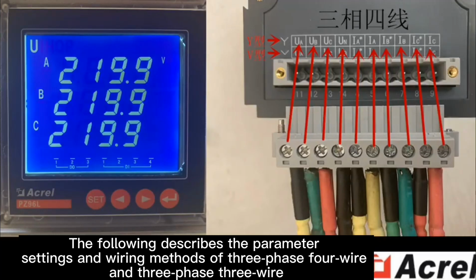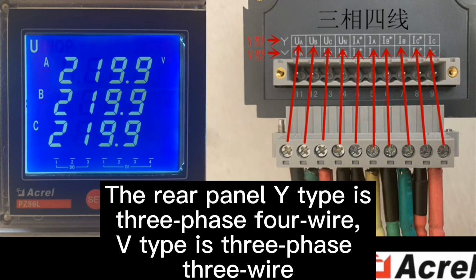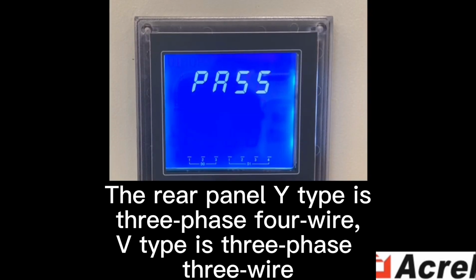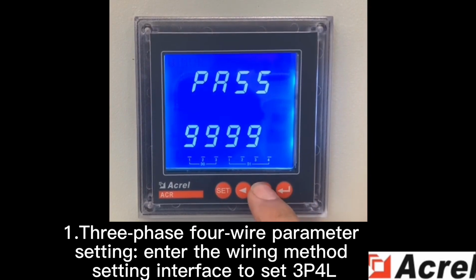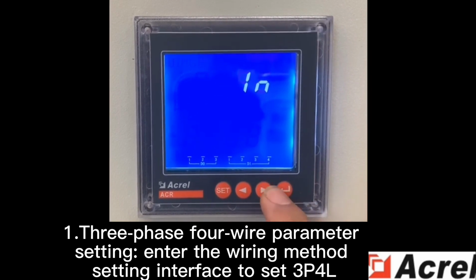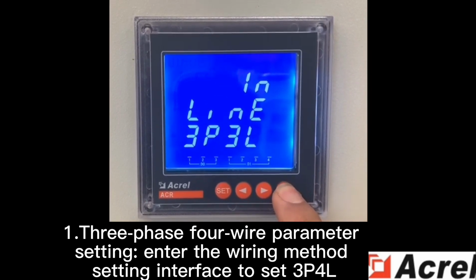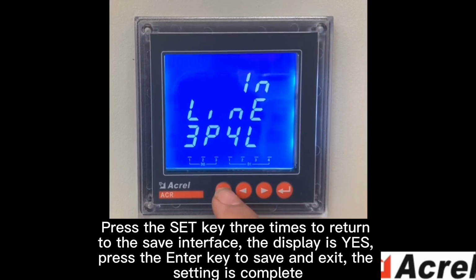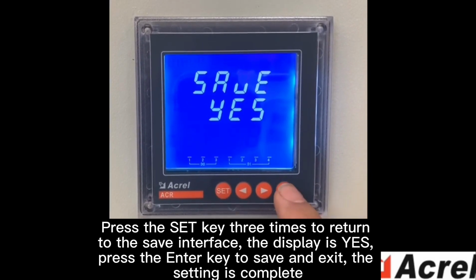The following describes the parameter setting and wiring methods of three-phase 4-wire and three-phase 3-wire. On the rear panel, Y type is three-phase 4-wire, V type is three-phase 3-wire. 1. Three-phase 4-wire parameter set. Enter the wiring method set interface to set 3P4L. Press the set key 3 times to return to the save interface. The display is YES.